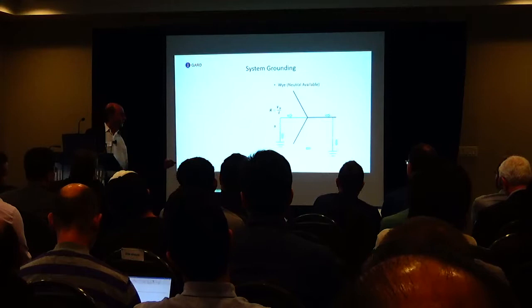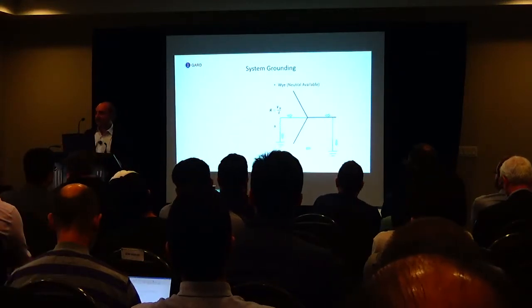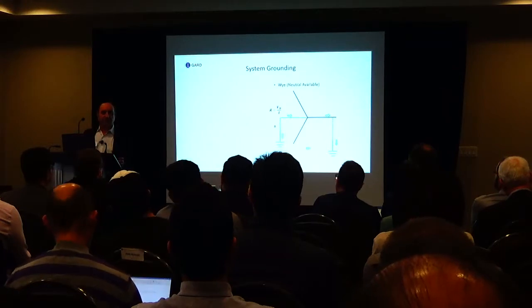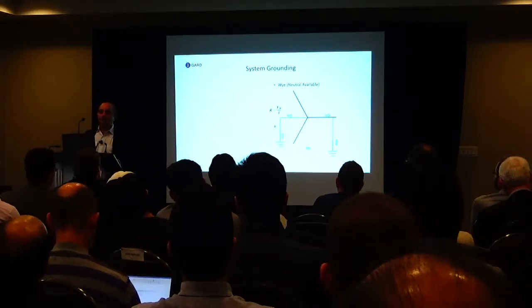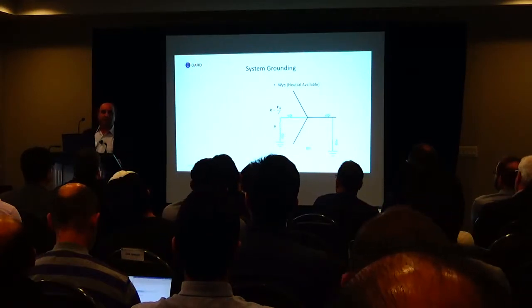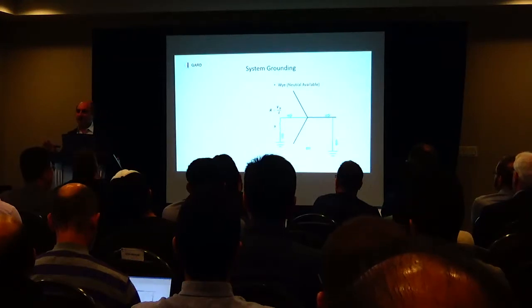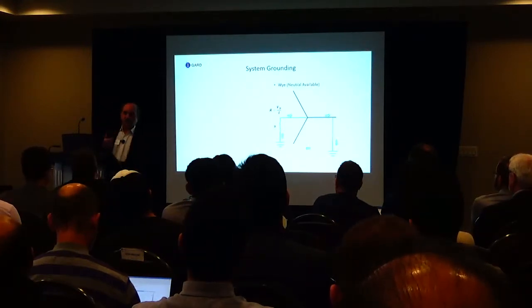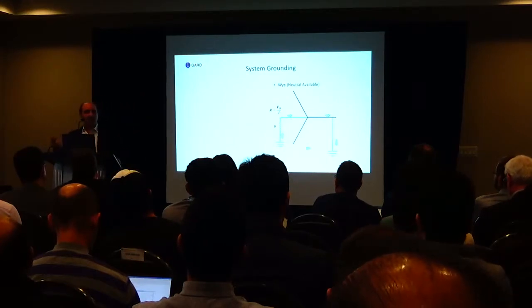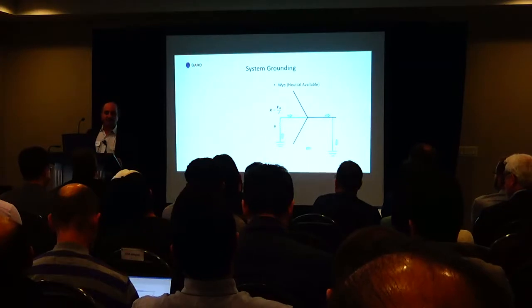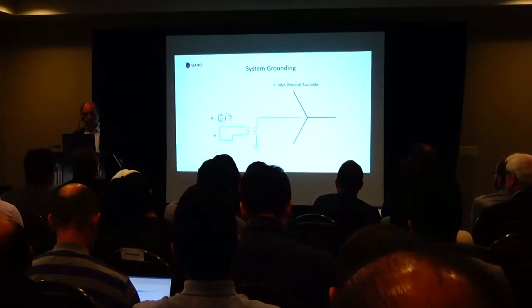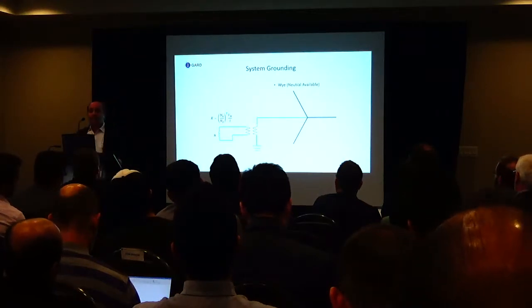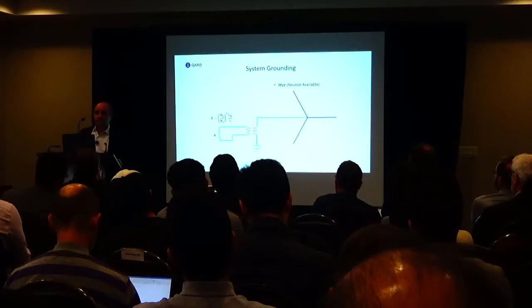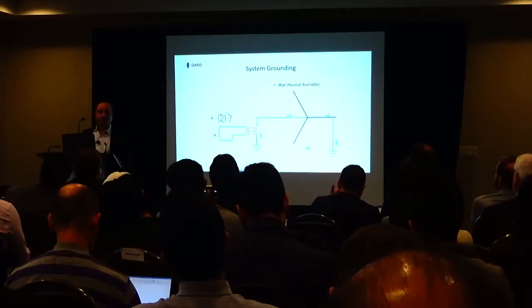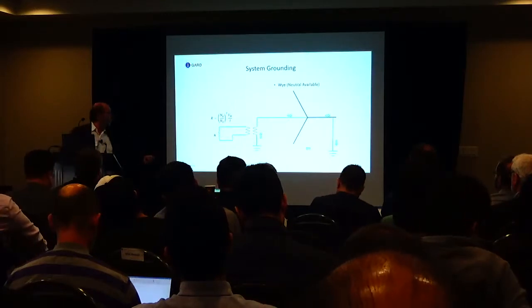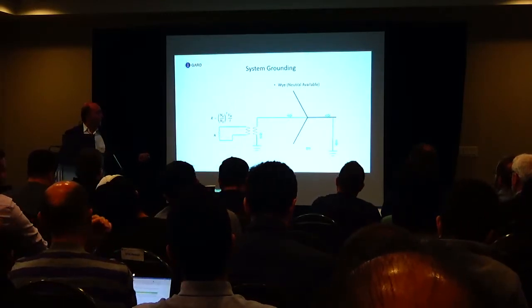So when you get a ground fault, current has to return back to the source. Ground fault current doesn't go to ground and just stay there. It has to return back to the source, and it uses the bonding network of your system to do so. I didn't spend a lot of time on the bonding network because regardless of whether you have an ungrounded system, a solidly grounded system, or a resistance grounded system, either low or high resistance, the bonding network is exactly the same. Sometimes if you have a generator, they use a step-down transformer and a resistor. Same thing happens. You get a ground fault, current is limited by the resistance on the secondary of the transformer, and this provides a path.